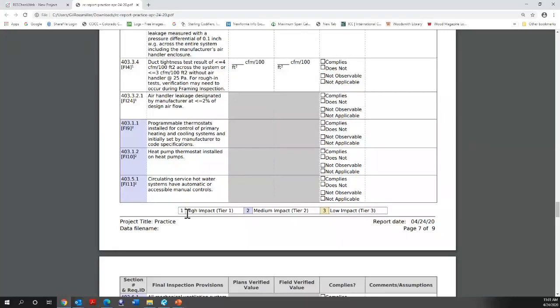And that's that example we looked at earlier, when you can actually calculate your other option, right? And Heather put in here, they enter the other in the description. Yes. Well, guess what? You can't do other. You can't say other and not give me your calculation, because all the software is going to do is say, oh, you've entered other, so tell me what your U value is for that assembly. That's all the software is going to ask. Okay? So they need to give you this is how I came up with this U value. This is what I used for my air film. This is what I used for my siding. This is what I used, so you can see the math. So that's very good. That's another one that they do. They say use other, put in what they want, so they pass. And then they can't give you their counts. They can't figure it out.